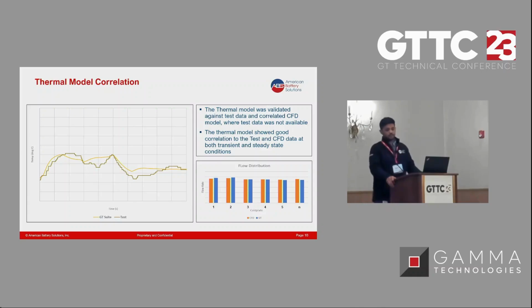Before testing the software with GT Suite, since we knew it's a very huge step, we took precautionary measures by running various correlations of the thermal model: steady state correlation, transient correlation, and flow correlation, using test data we tested in-house. Information like flow distribution in cold plates is very hard to get from test data, so we relied on CFD data for that, and the CFD model is correlated as well.